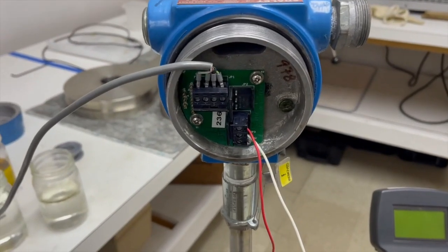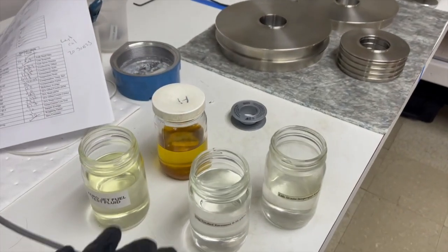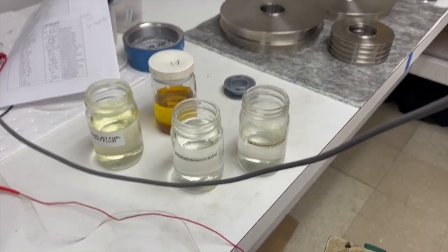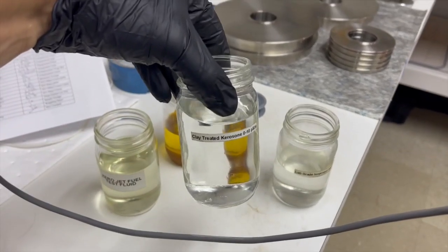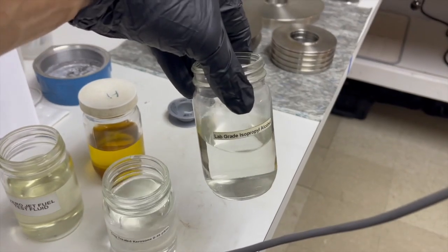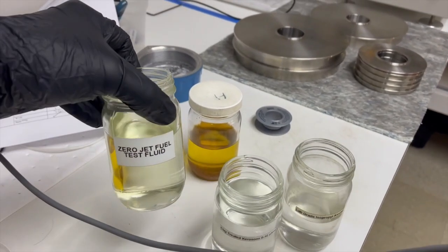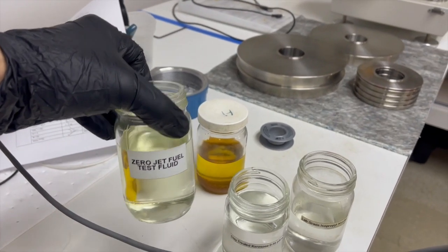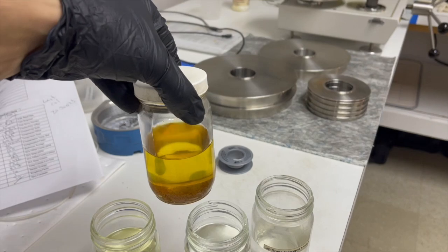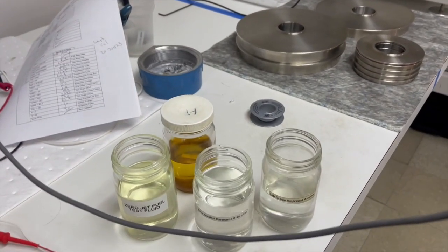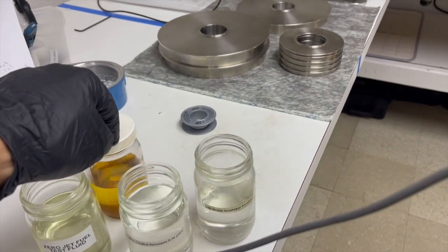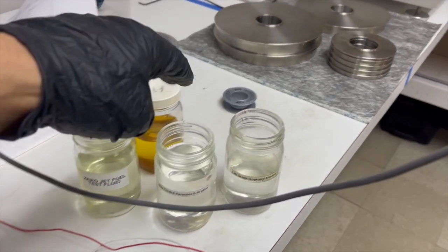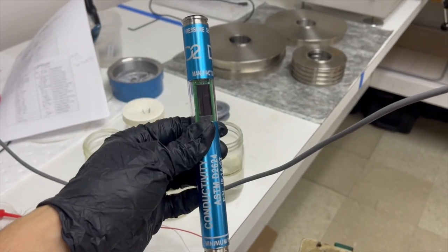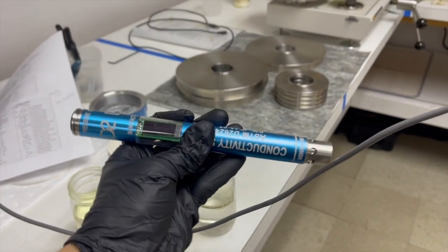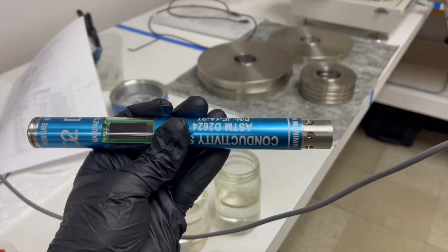Okay, so once we are ready to calibrate conductivity, we'll have our fuel samples and our isopropyl alcohol ready to go. We have here our zero fuel. We have our lab grade isopropyl alcohol, 99%. We have our conductivity of about 800 fuel. And we have our conductivity of somewhere around 1600 fuel. In order to do a linear calibration again, we're going to get a 0 value and a high value, calibrate with those, and then we're going to verify with all 3 that the calibration is correct. And we're going to use this as our verification device, as I've already shown you that we have verified and/or calibrated this before running this test.